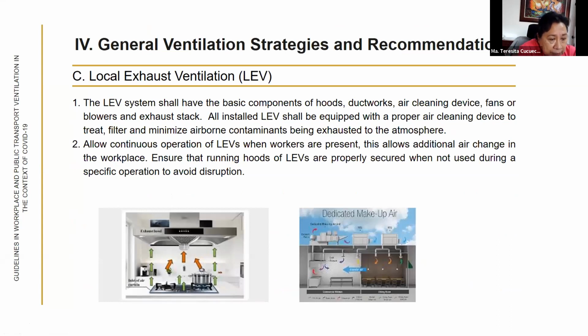In many workplaces like restaurants and even in hotels, or in the manufacturing industry, or where work involves the use of chemicals, or here in cooking, there will be local exhaust ventilation. Local exhaust ventilation is another means of removing stagnant air or indoor air that would produce smoke or would have contamination. And this local exhaust system shall have the basic components of the hood, the ductwork, the air cleaning device, the fans or blowers, and the exhaust stack. So all of these LEVs should be equipped with the proper air cleaning device before the air is brought out, so that the air that passes through it will be purified before it is released.